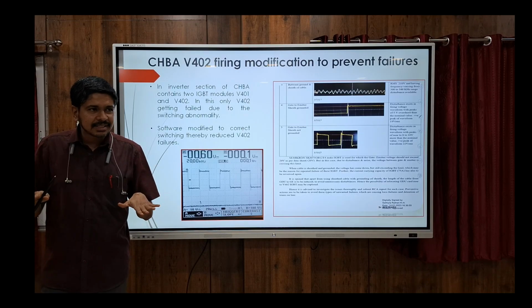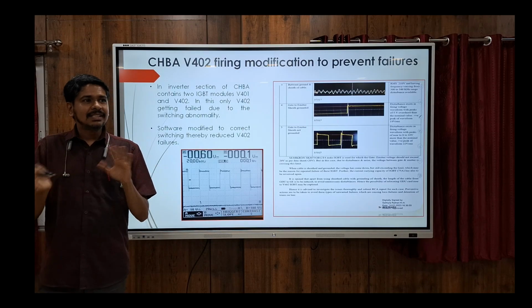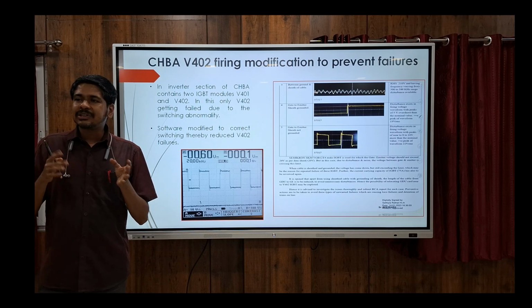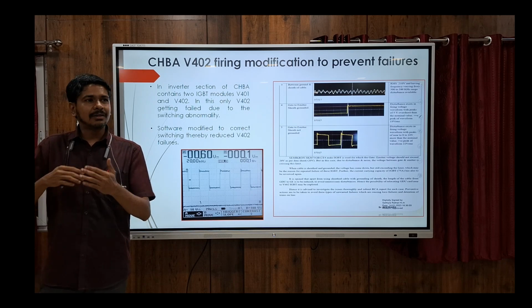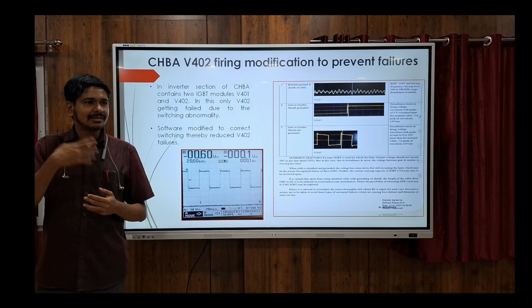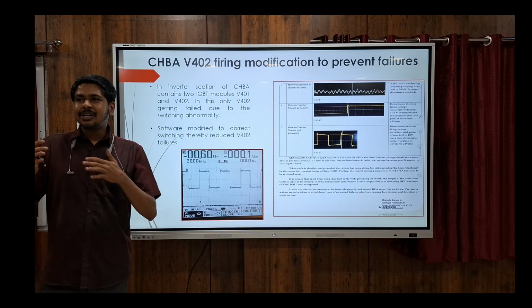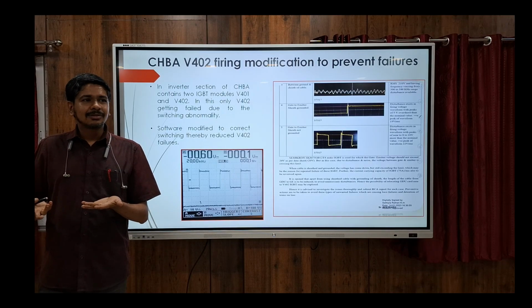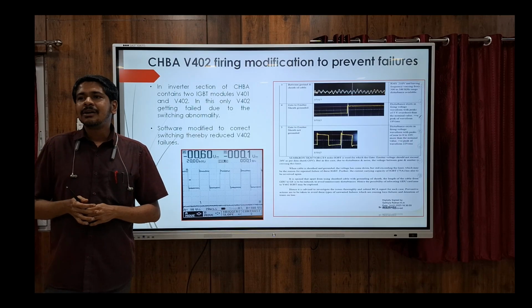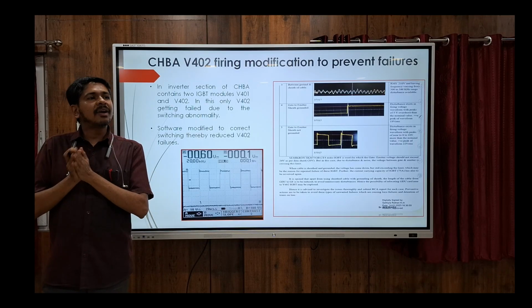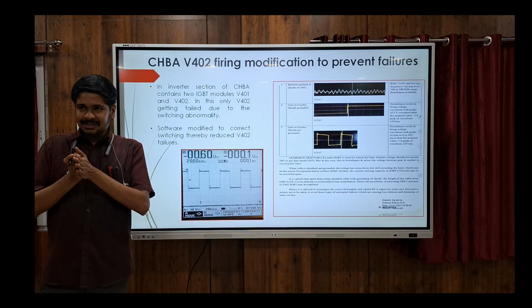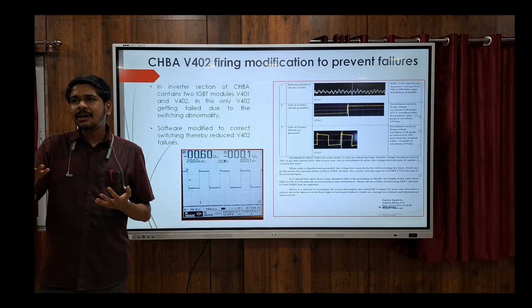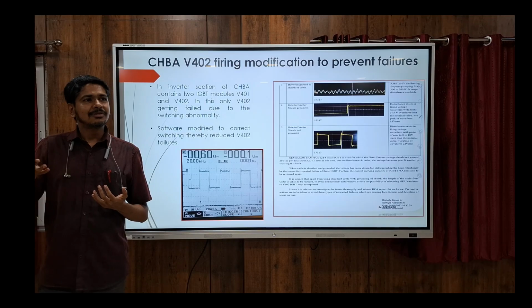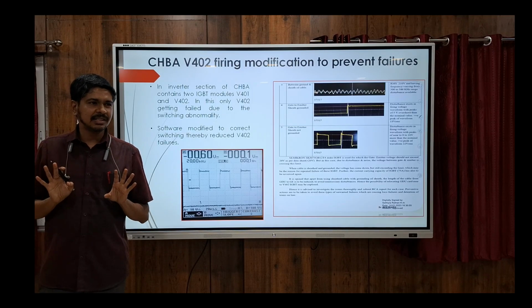Actually, in normal conditions, both IGBTs, or both legs, should carry equal load. But in case of V402, it was slightly more. If it carries more load, it fails sooner. So we identified that the firing pattern for V402 was imposing a heavy duty cycle, and it was causing failure of that IGBT, and the battery charger was failing.